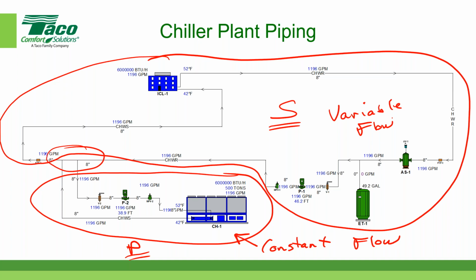Now, let's assume that, again, this is a simple office building. There's nothing complex going on here. If that's the case, then chances are that we can reduce the flow on the secondary circuit, and usually the limiting factor is the pump itself. And so we say that the pump can go down to roughly one third its flow. But if you use multiple pumps, let's say if you use 2 pumps and each one was sized for 50% capacity, then that means that you're going to be half of 1/3 or 1/6 of flow. So you can see on the secondary side, you can reduce the flow significantly and save a huge amount of horsepower. On the primary side, you have to have constant flow.